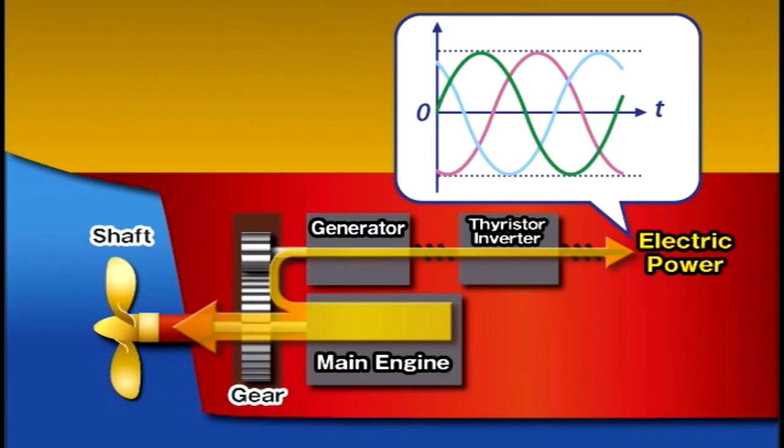In this shaft generating system, the frequency of the generating voltage remains unstable because the number of output shaft rotations varies according to ship speed. Thyristor inverters are used in shaft power generators to resolve this problem.